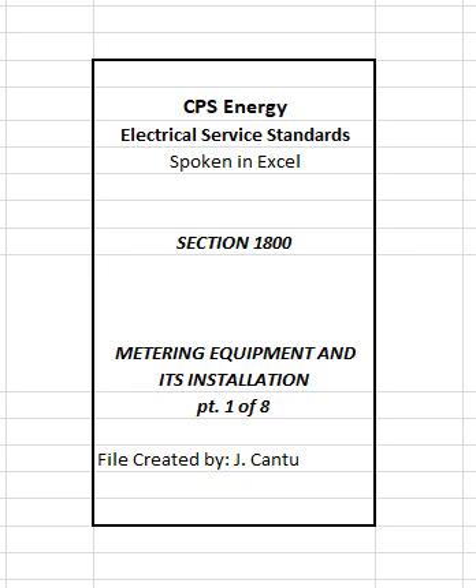A. Particular attention must be paid to identification and placement of the high leg conductor in sockets being wired for 240 delta/120 volt, 4-wire services, refer to Figure 1808. The high leg conductor has 208 volts to neutral and shall, for proper metering equipment operation, be in the farthest right-hand position, C phase position, facing the meter socket. However, NEC rules require that the high leg conductor occupy a center position in customer's service equipment and be identified as B phase. B. The high leg conductor must be identified orange in color. CPS Energy may, for its operations, identify the high leg at its transformer, service, or other location as a phase other than B.